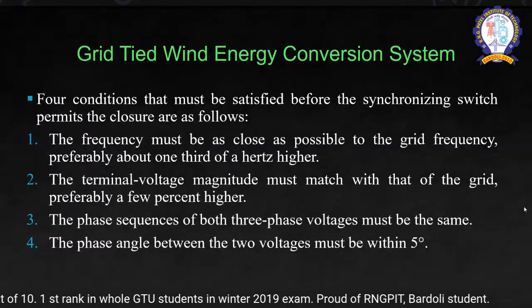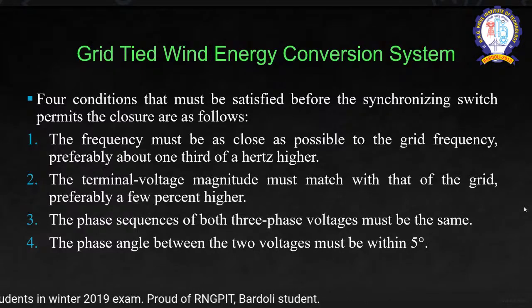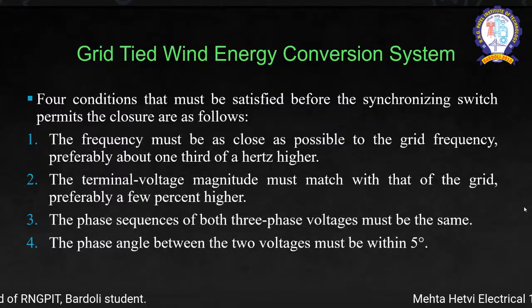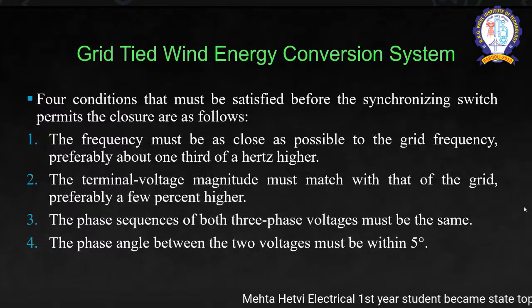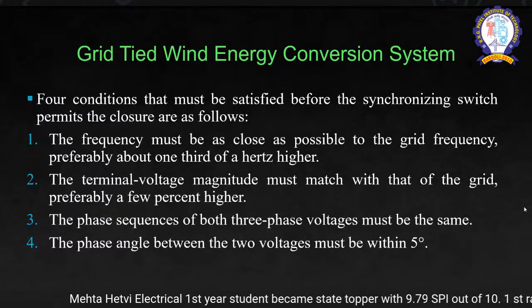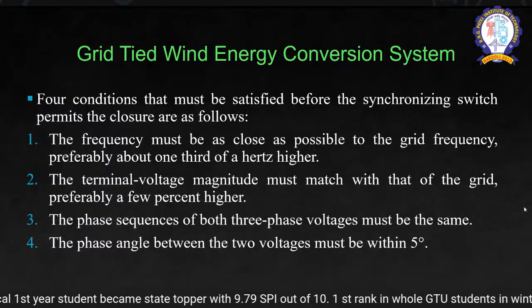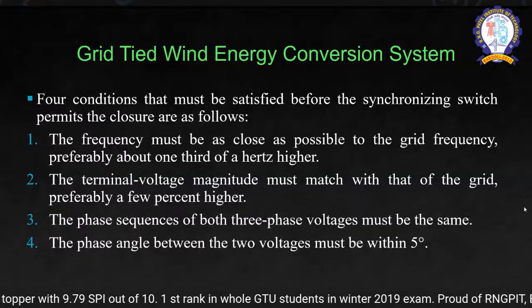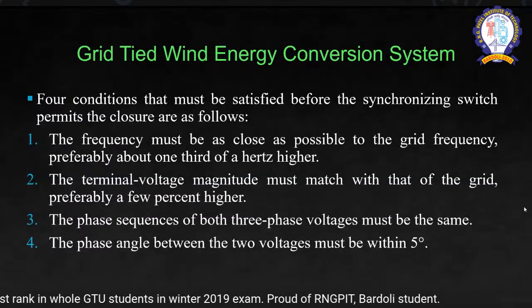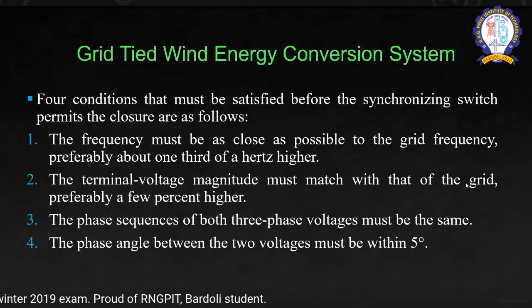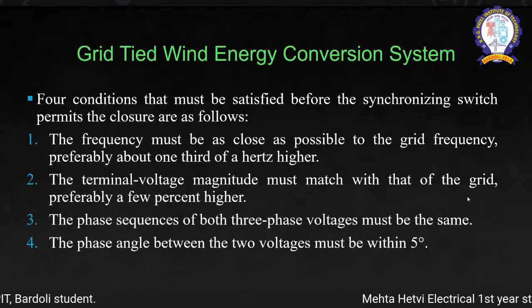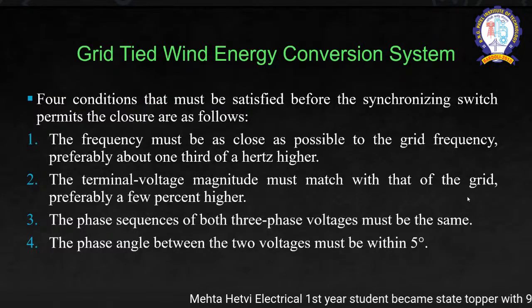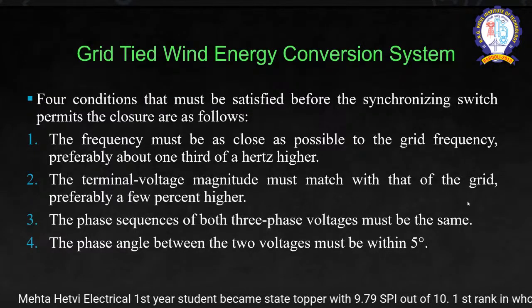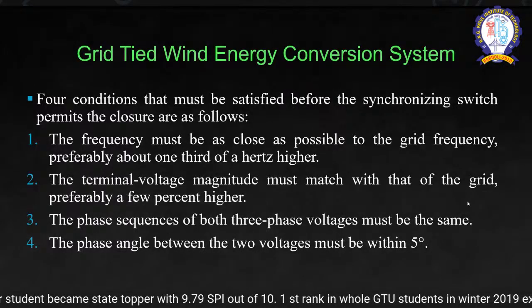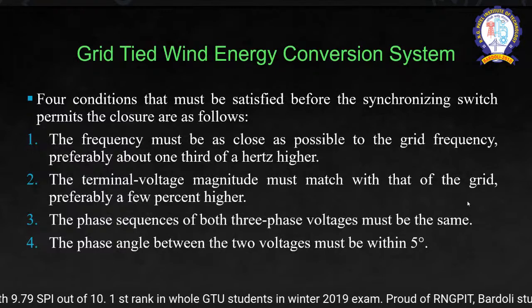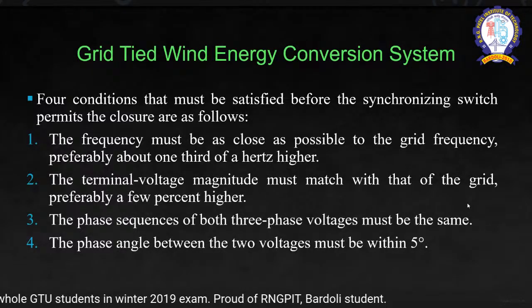Now, in case of the frequency limit, we have a band of 1 hertz, that is 49.5 hertz lower and 50.5 hertz upper. Within that band, we need to integrate this wind farm. So what we need to maintain is that the frequency must be as close as possible to the grid frequency, preferably 1/3 of a hertz higher, because we need to push the power into the grid. The terminal voltage must be matched with that of the grid voltage, preferably a few percent higher, so you can pump the electrons into the grid.